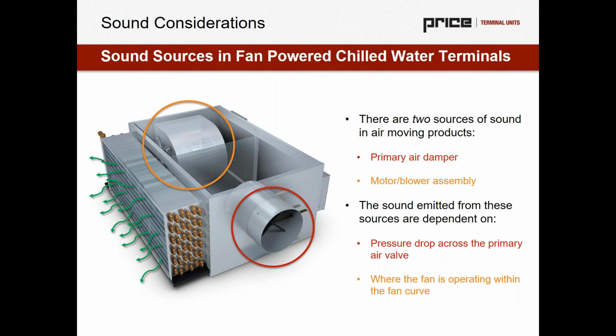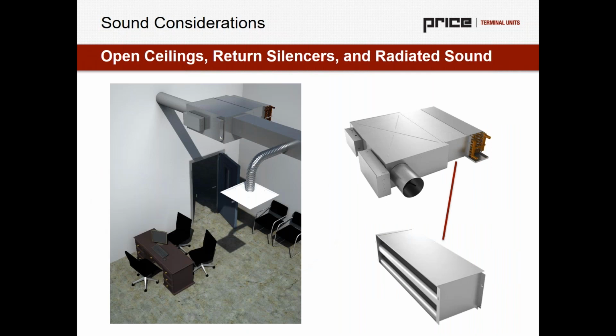I don't want to scare anyone away from using this type of system, even in sound critical applications. Recently, me and Brian have worked on a project where we're up to 1600 CFM in an open ceiling, still providing an NC35, which is very acoustically comfortable, especially for an office. But that project and many projects would require the utilization of an RSLR, or our return silencer, which is going to essentially stop sound from breaking out through that coil. And that's the sound that's generated both by the motor and the primary air inlet there.